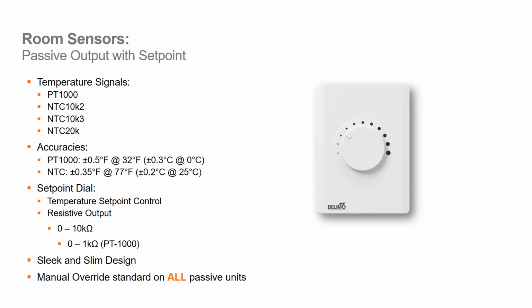We offer passive set point, which is pretty common in a lot of applications. So again, the same passive sensor ratings, PT1000, 10K type 2s, type 3s, 20K NTCs, same accuracies. They have a set point dial with a resistive output. The majority of them are going to be a 0 to 10 kilo ohm output, except for the PT1000 model, which is going to have a 0 to 1 kilo ohm output. Again, nice clean Belimo design, and override is standard on all the passive units.